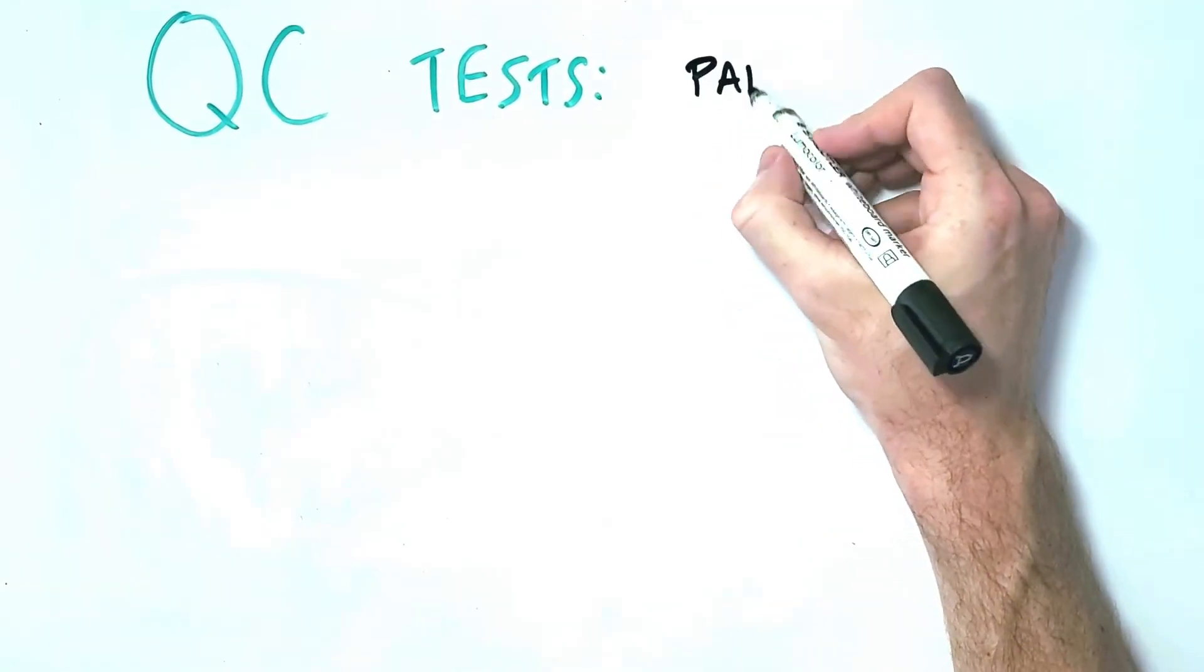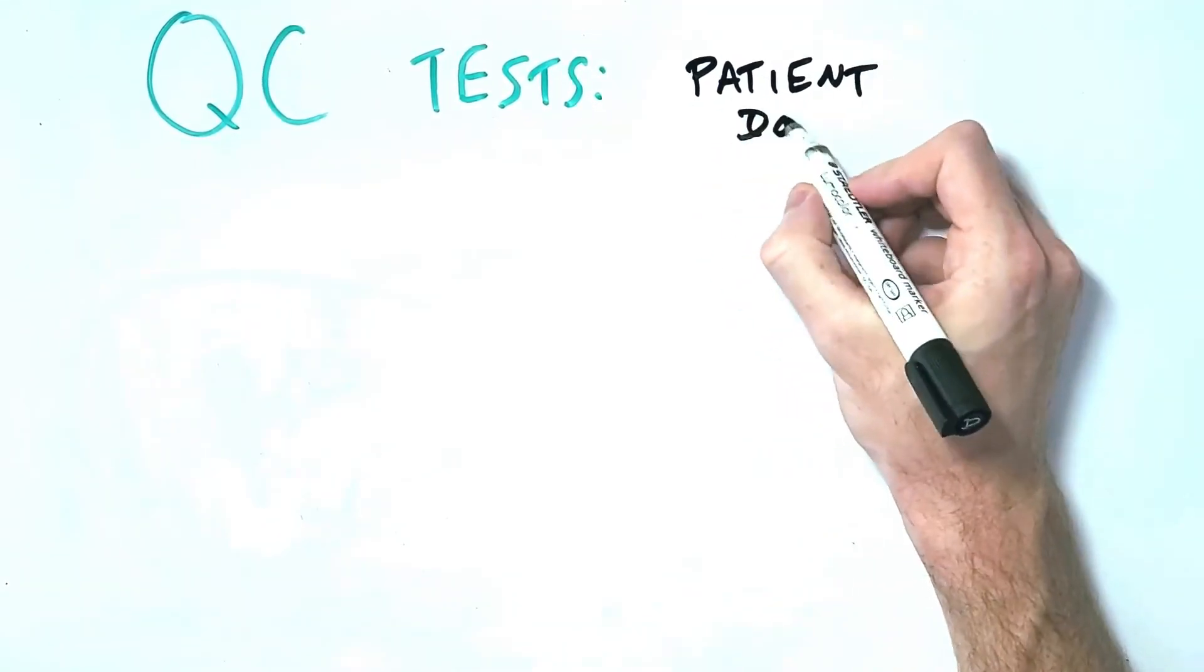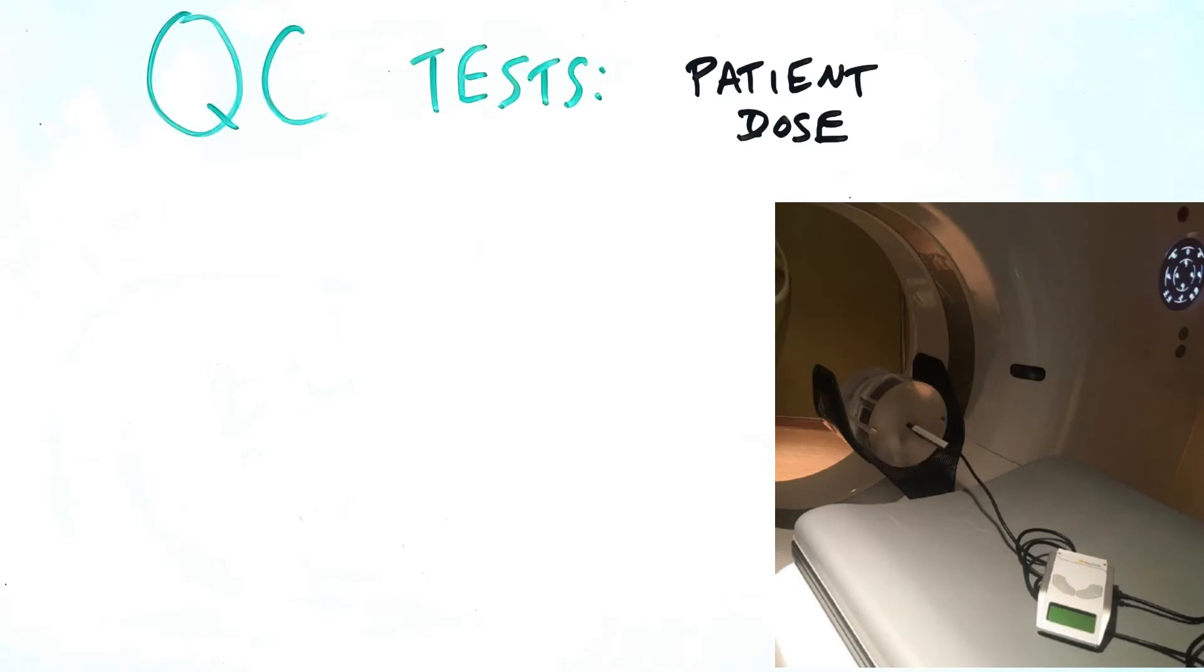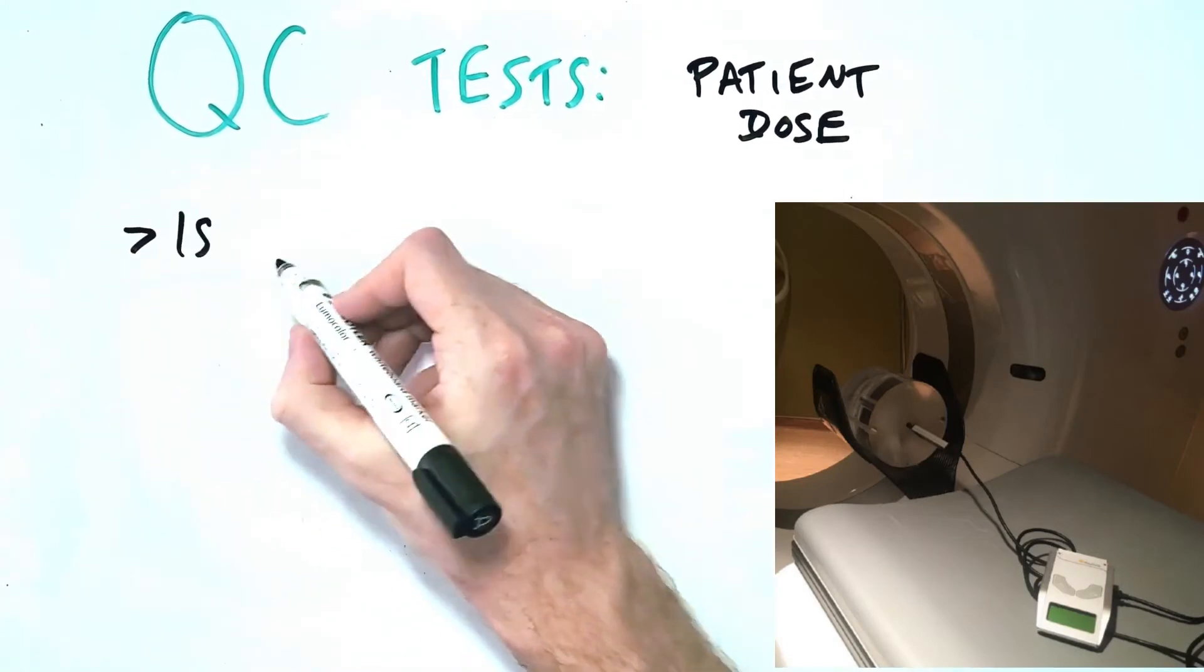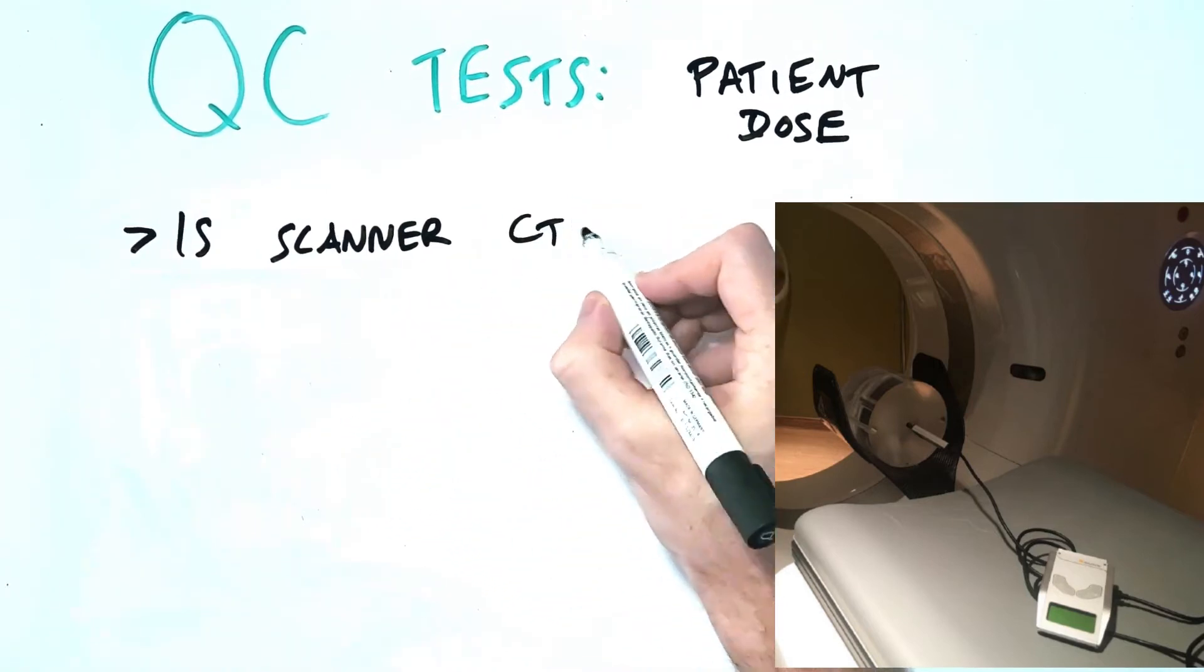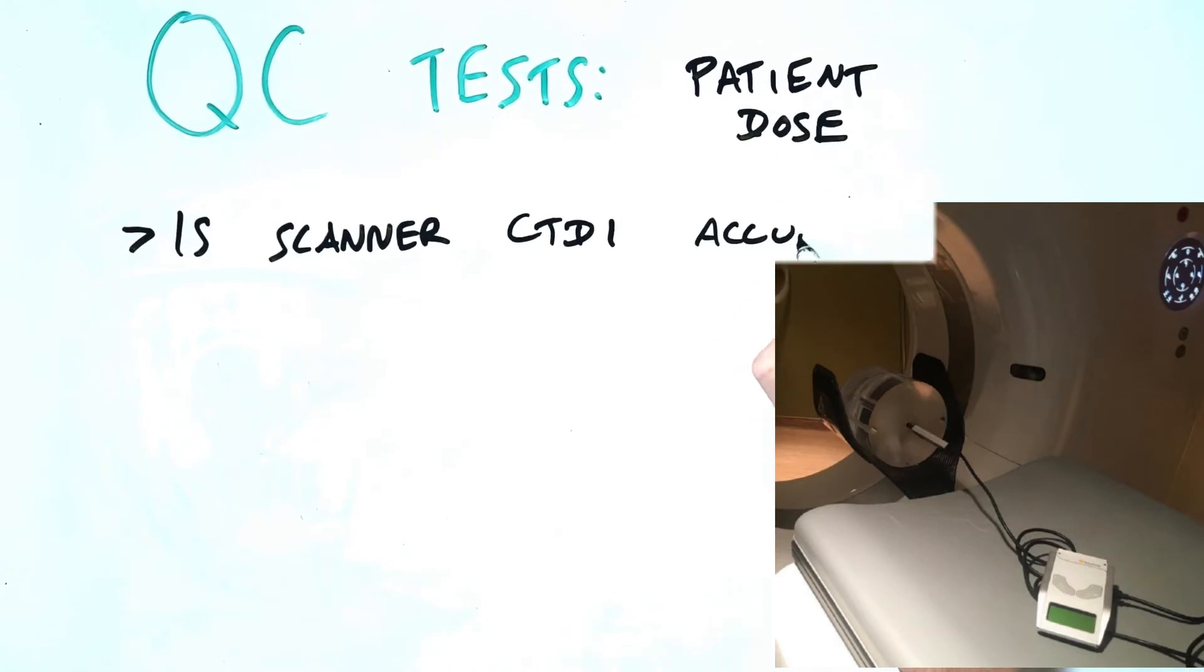Finally, the patient dose should be measured to assess whether the CT dose index displayed by the scanner is an accurate assessment of the dose being delivered to the patient. Some level of variability from the true dose is acceptable, but the primary purpose of the displayed CTDI and DLP for each scan is to compare to reference levels, to compare to other scans performed on that same scanner.